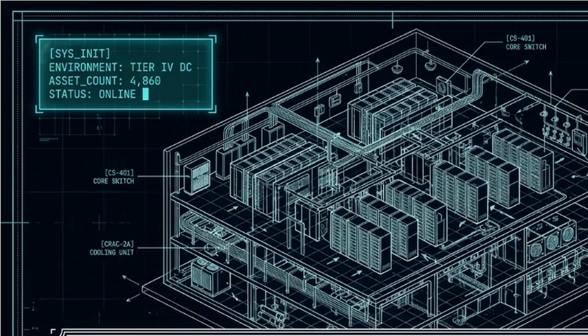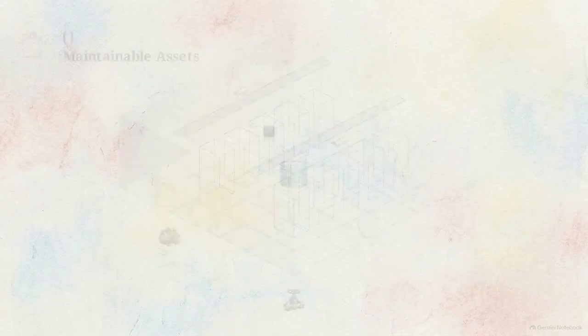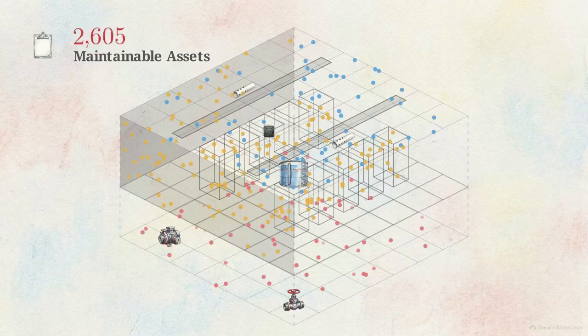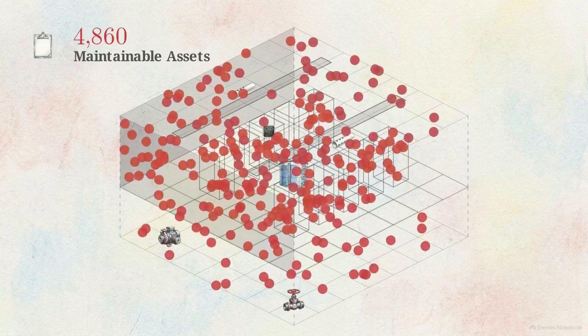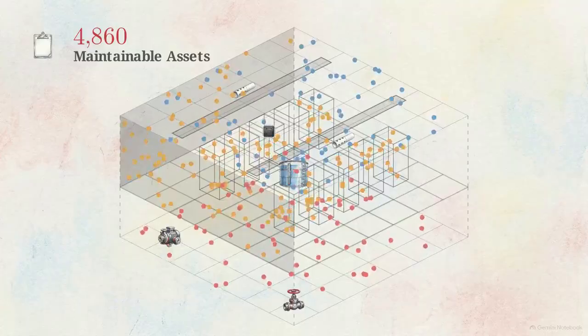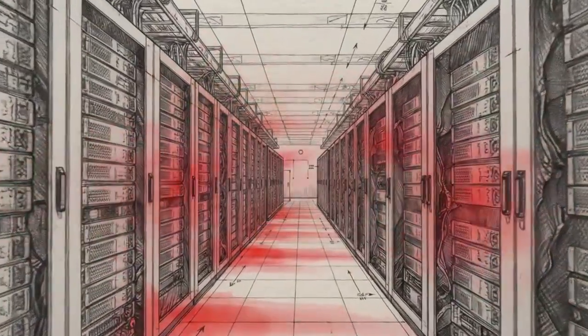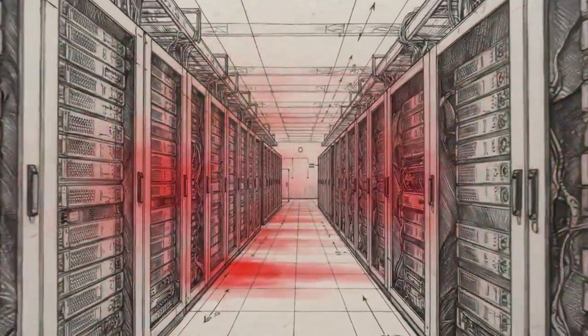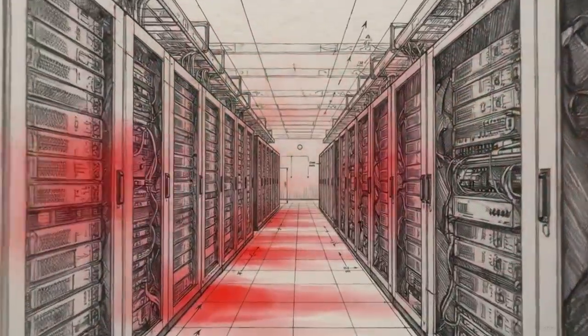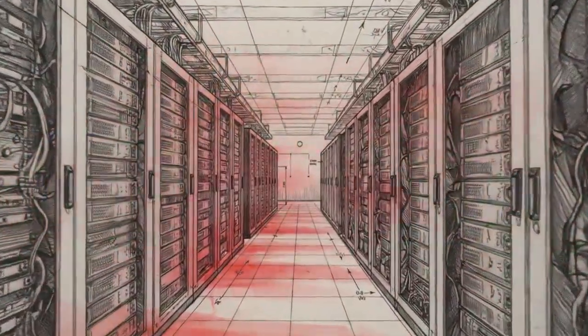This schematic displays a Tier 4 data center, an environment defined by fault-tolerant power and cooling paths designed for zero downtime. To reach this Tier 4 standard, nearly 5,000 maintainable assets are synchronized to protect the facility. Yet, billion-dollar data centers still experience catastrophic failures that take them offline, despite passing every commissioning test on day one.